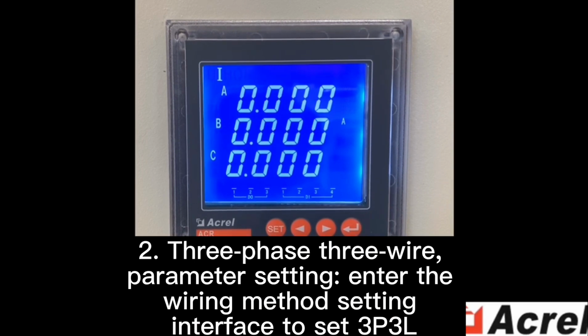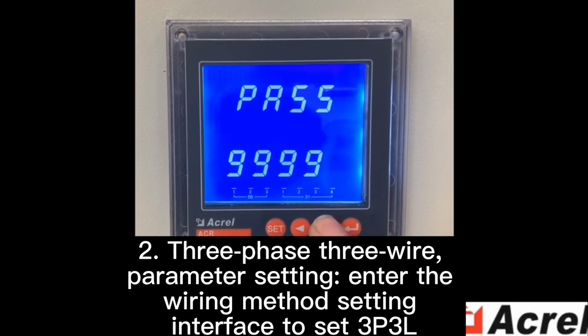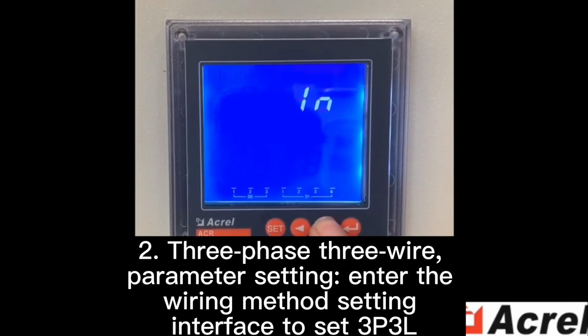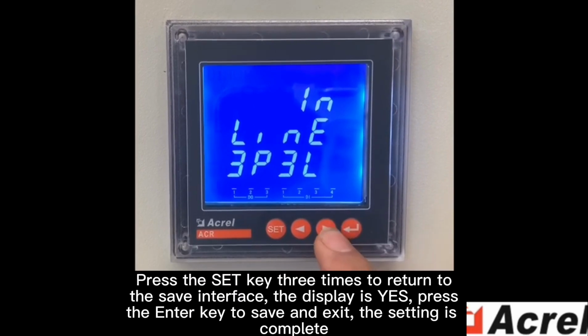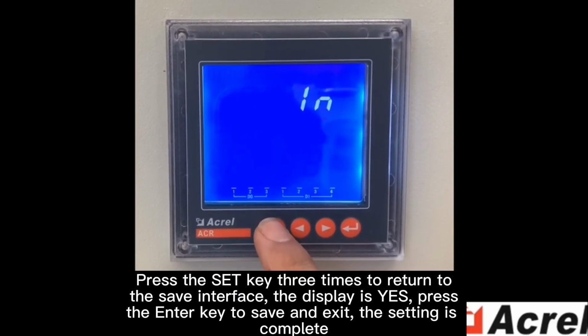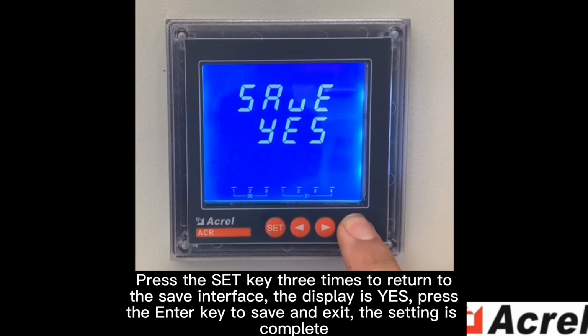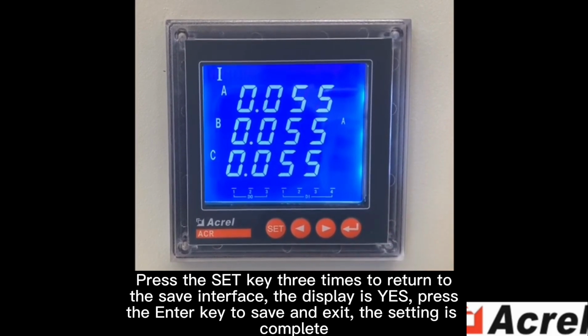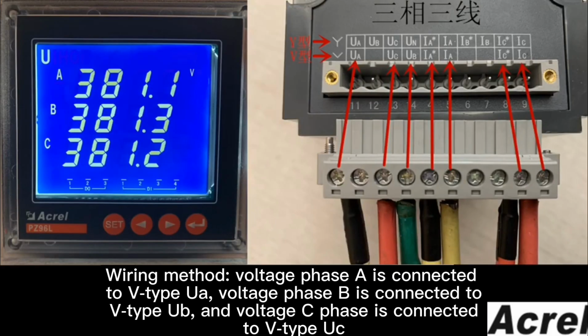2. Three-phase 3-wire parameter setting. Enter the wiring method set interface to set 3P3L. Press the set key 3 times to return to the save interface. The display is YES. Press the enter key to save and exit. The setting is complete. Wiring method.